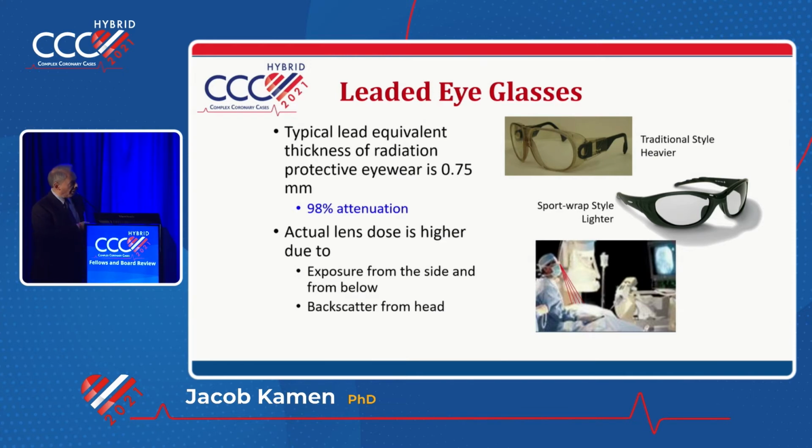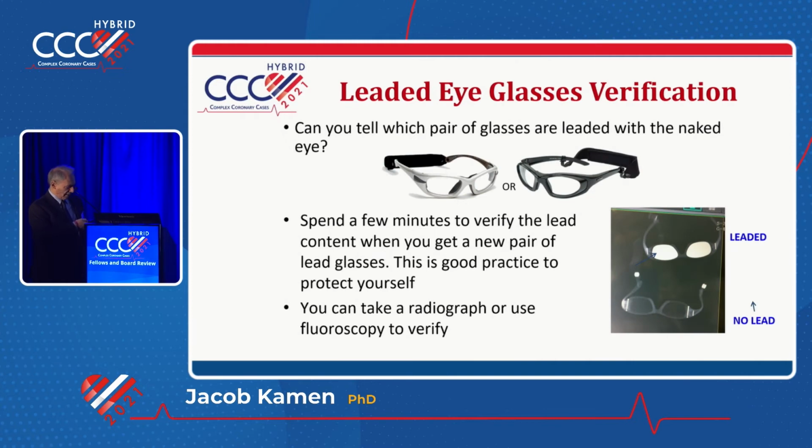Now, sometimes in the market, they sell you something that is fake. So all you have to do is take the lead glasses and put them under the fluoro, and you will see if it whitens, that means it's lead. If there is no reaction, that means there is no lead in it. It takes less than a minute.